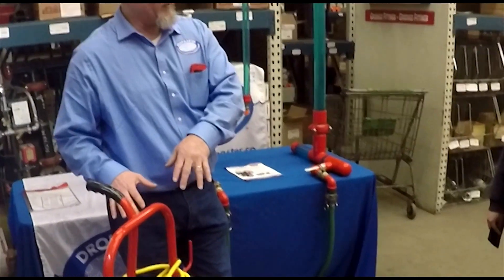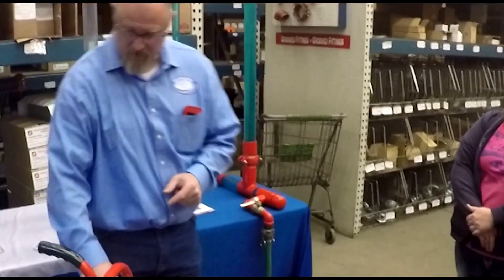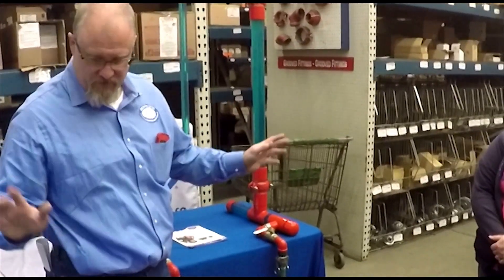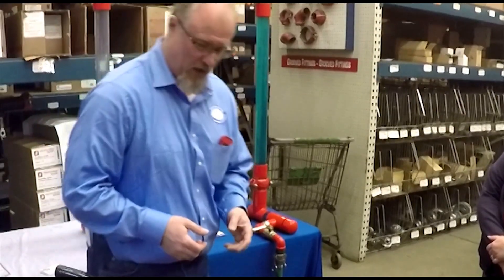You need to drain this down daily. If you do not drain the oil out of this muffler every day and it fills up with oil, from that muffler — 16 feet back and about 12 foot square — you are going to cover everything in oil. It does a tremendous job of making a mess. So every day, drain the oil out and you won't have any problems.